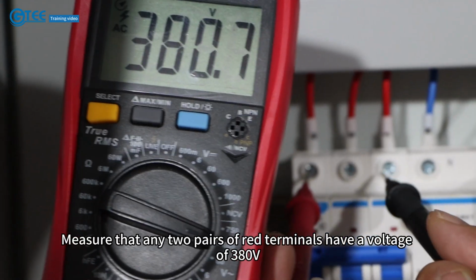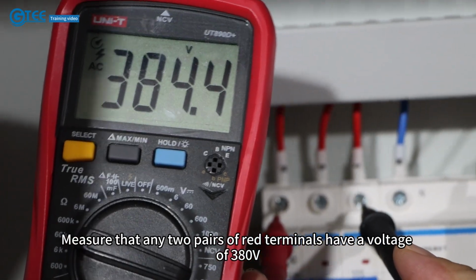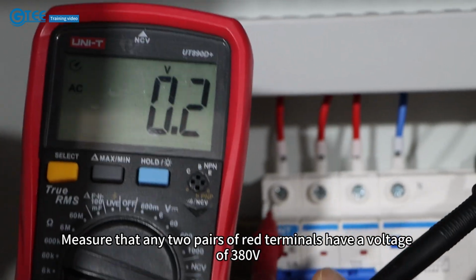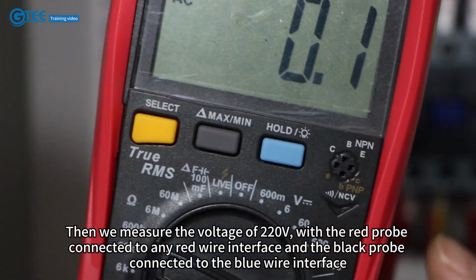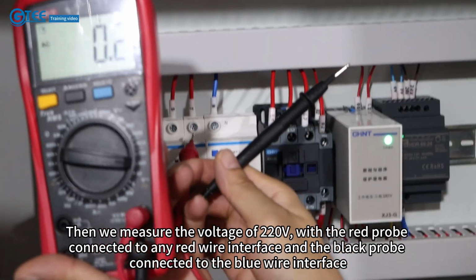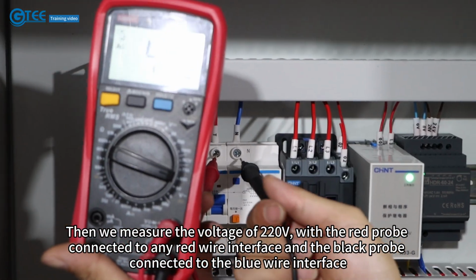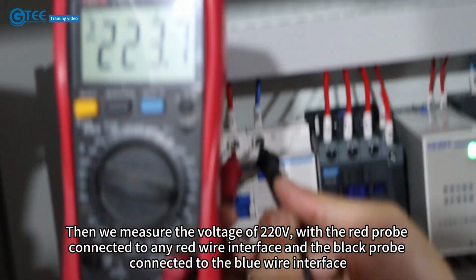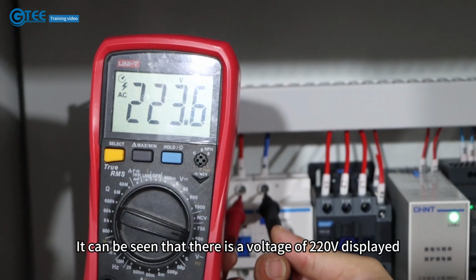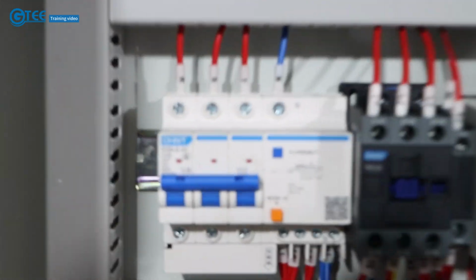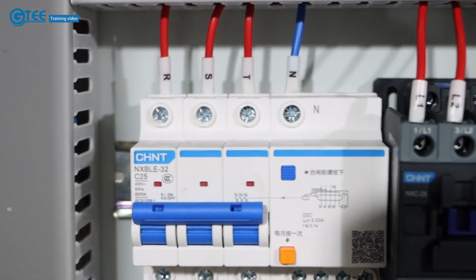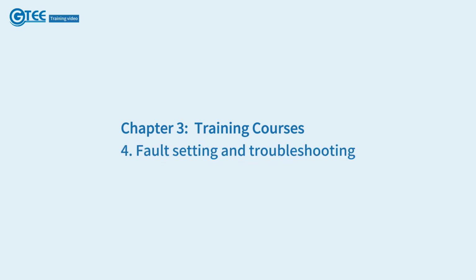Measure that any two pairs of red terminals have a voltage of 380 volts. Then we measure the voltage of 220 volts with the red probe connected to any red wire interface and the black probe connected to the blue wire interface. It can be seen that there is a voltage of 220 volts displayed. Signal test completed. 4. Fault setting and troubleshooting.